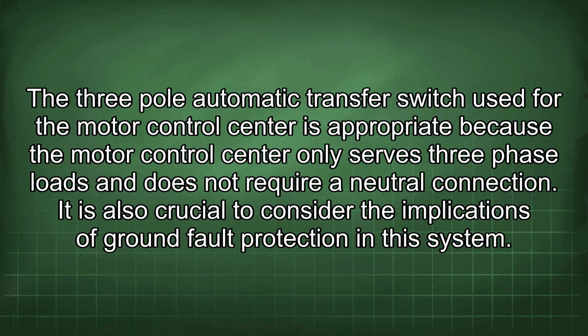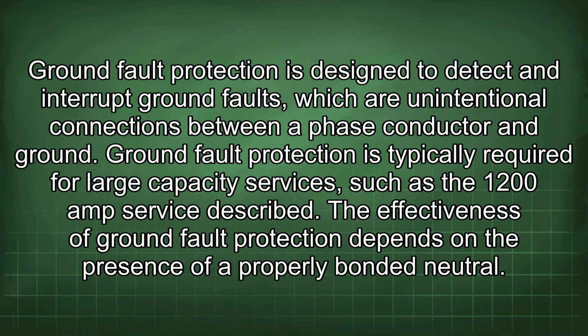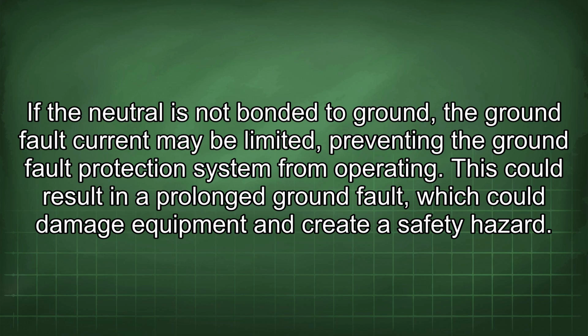It is also crucial to consider the implications of ground fault protection in the system. Ground fault protection is designed to detect and interrupt ground faults, which are unintentional connections between a phase conductor and ground. Ground fault protection is typically required for large capacity services, such as the 1200 amp service described. The effectiveness of ground fault protection depends on the presence of a properly bonded neutral. If the neutral is not bonded to ground, the ground fault current may be limited, preventing the ground fault protection system from operating. This could result in a prolonged ground fault, which could damage equipment and create a safety hazard.